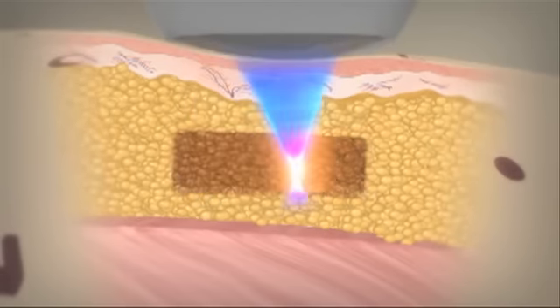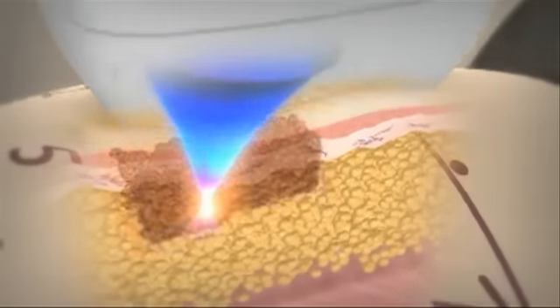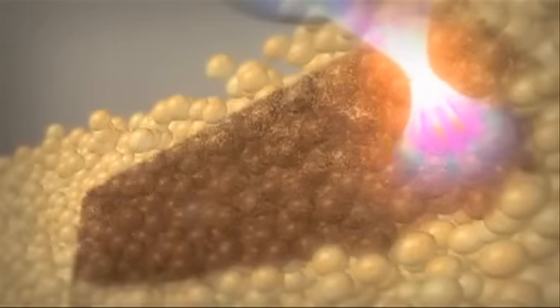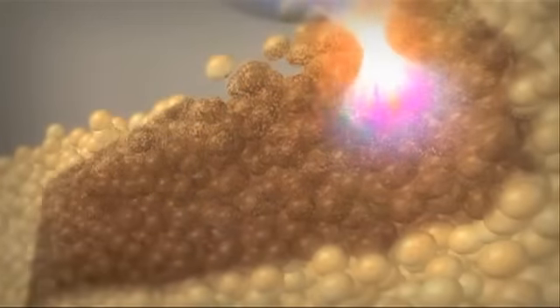While the treatment head is held in place, the Liposonix pattern generator automatically moves the high-frequency ultrasound transducer, treating a consistent uniform area of abdominal fat tissue. The operator then moves the head to the next treatment area. This process continues until all sites are treated.